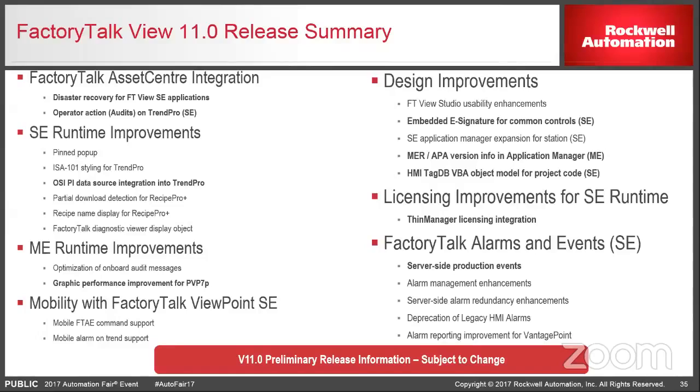open up as many instances of it as I want, and one license covers it because I'm logged in as me. When we get into Thin Manager, you have to actually have separate logins in order for it to handle that type of remote connection. So it was resulting in if I had 4 displays, 4 FactoryTalk View SE displays on one thin client, it would actually eat up 4 view licenses.